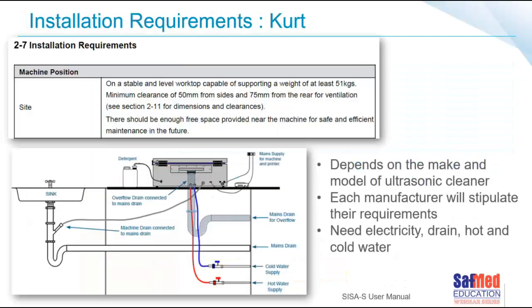Right, so we need now a bath. What are we going to do? How do we install our bath? Kurt, can you give us some guidelines? 100%. Okay, so the installation requirements of an ultrasonic cleaner will vary from brand, make, and model. And the example that we currently have on the screen starts off with that, with all ultrasonic cleaners, we need to start off with a stable and level worktop which accommodates the brand, make, and model. We also need to ensure that there's enough clearance around the ultrasonic cleaner. It's for ventilation. It's also for future maintenance work by technicians and storage of your detergents and your lower pipes and connectors.